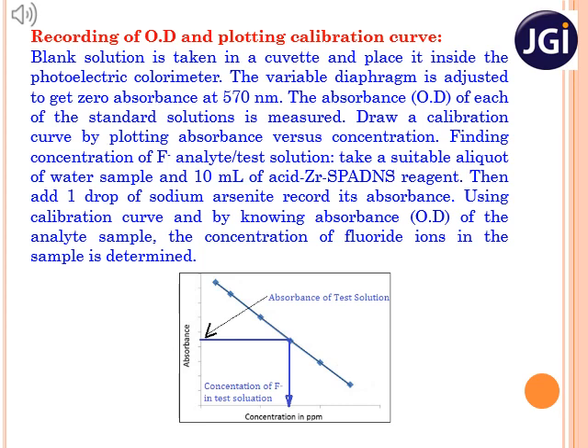The last step of analysis is recording the optical density or light intensity and plotting the graph. Another name for optical density is absorbance — optical density and absorbance are the same. This graph is called a calibration curve. The sample holder is called a cuvette. Blank solution is taken in the cuvette and placed inside the photoelectric colorimeter. The wavelength of maximum absorption is set to 570 nm. The optical density of each standard solution prepared previously is measured.